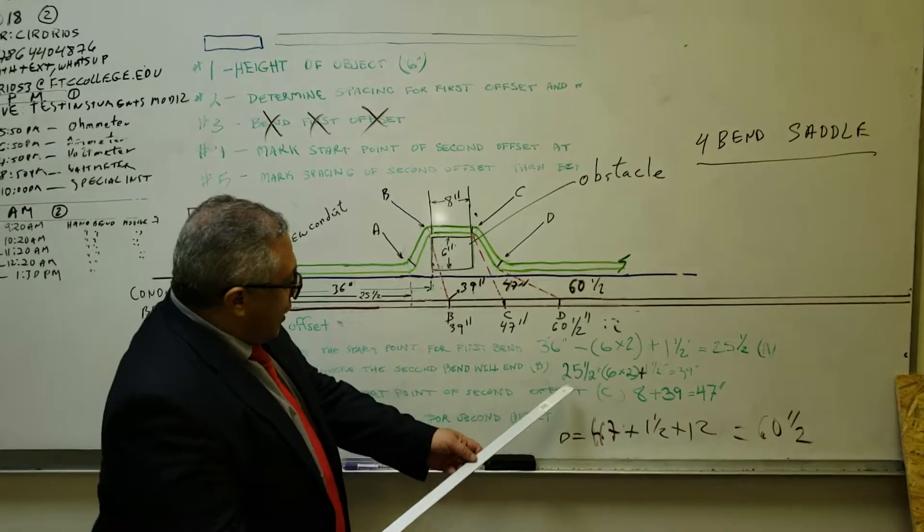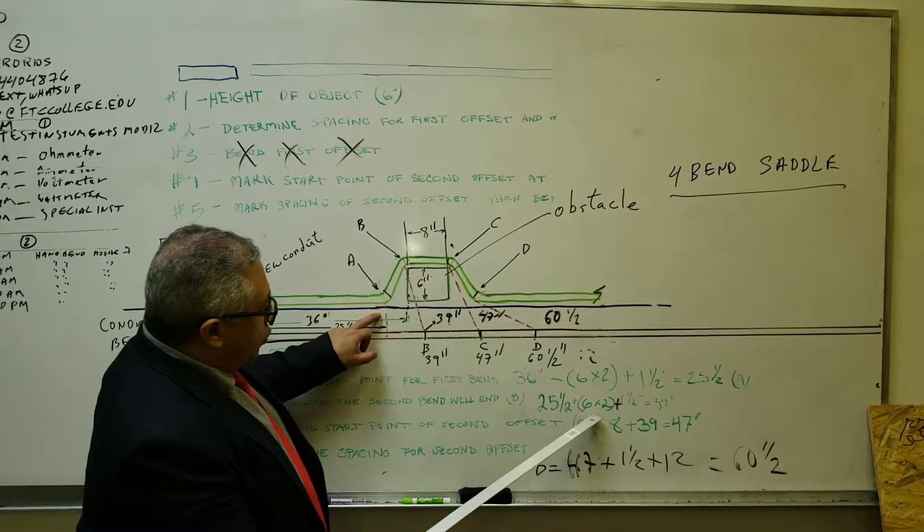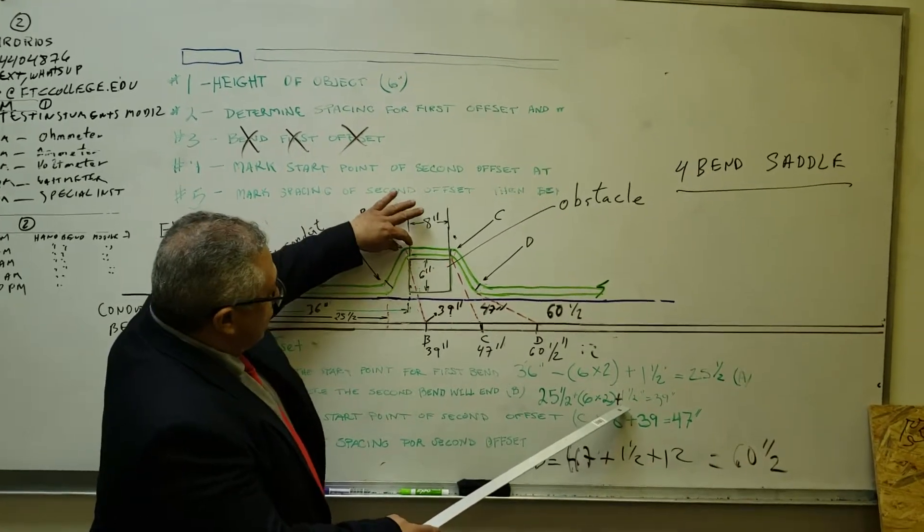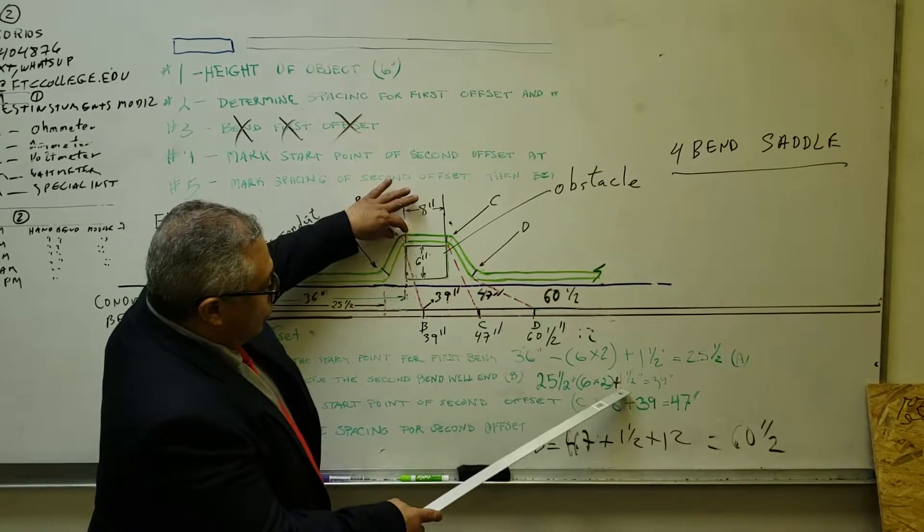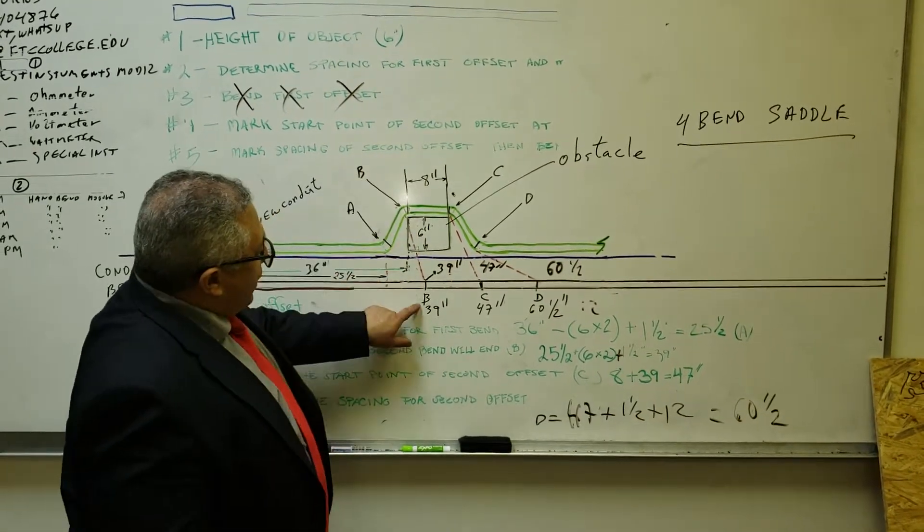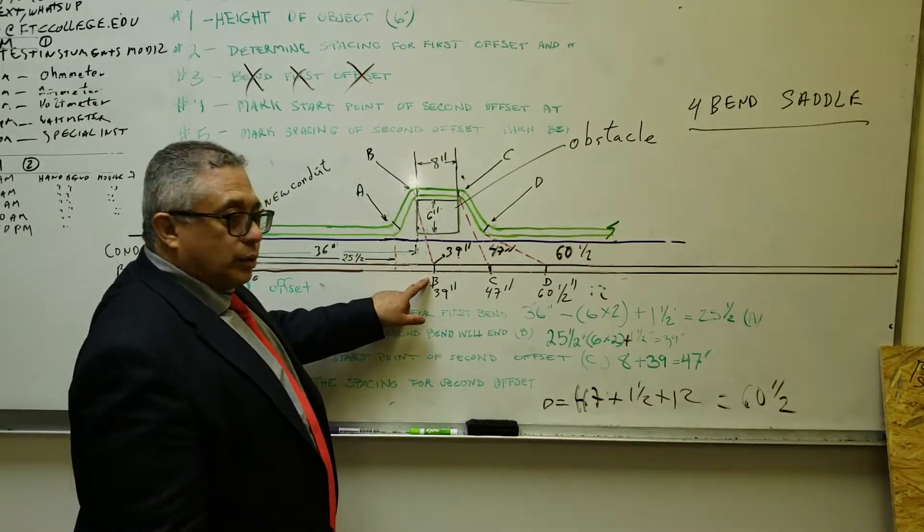So you have 25 and a half plus the multiplier times the height, which is 12, plus the shrink value, which is 1 inch and a half, and that gives us 39. That's point B, and we mark this in the conduit.